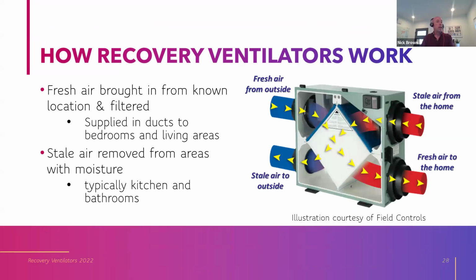Here's another cutaway of the heat exchanger core. You see this one is showing kind of standard filters on the exhaust and supply. All those are doing is protecting the fans from wear and tear, catching the bugs. In a code compliant California installation, you'd have a MERV 13 filter on that fresh air from outside.